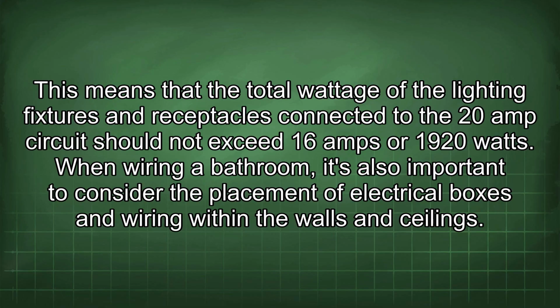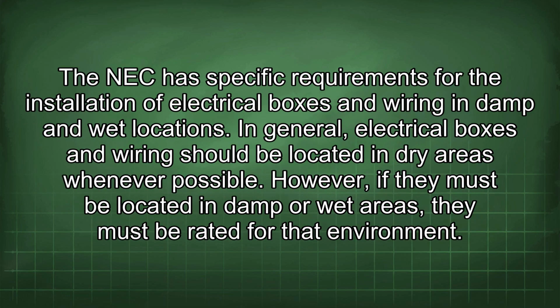When wiring a bathroom, it's also important to consider the placement of electrical boxes and wiring within the walls and ceilings. The NEC has specific requirements for the installation of electrical boxes and wiring in damp and wet locations. In general, electrical boxes and wiring should be located in dry areas whenever possible. However, if they must be located in damp or wet areas, they must be rated for the environment.